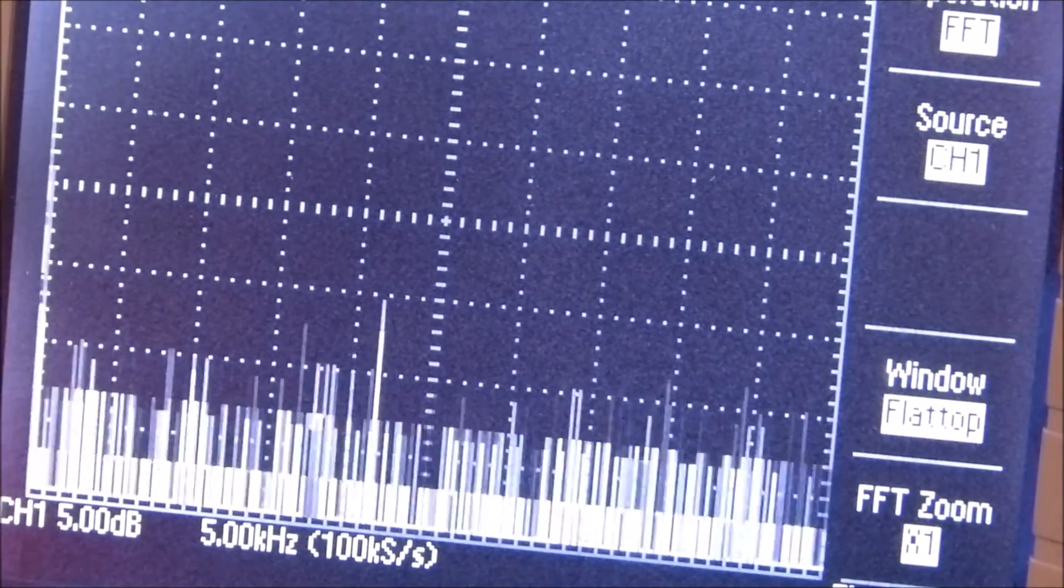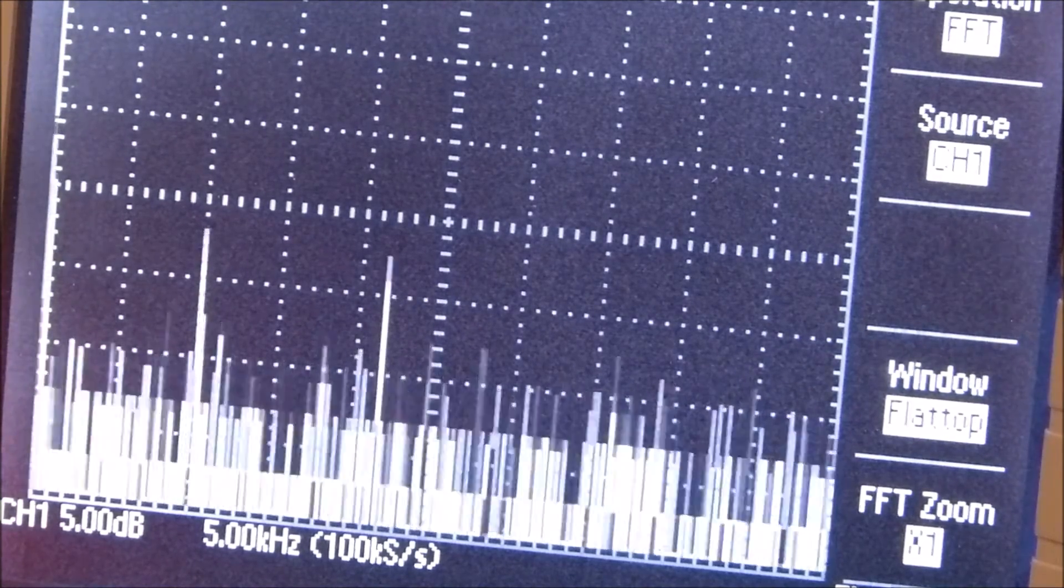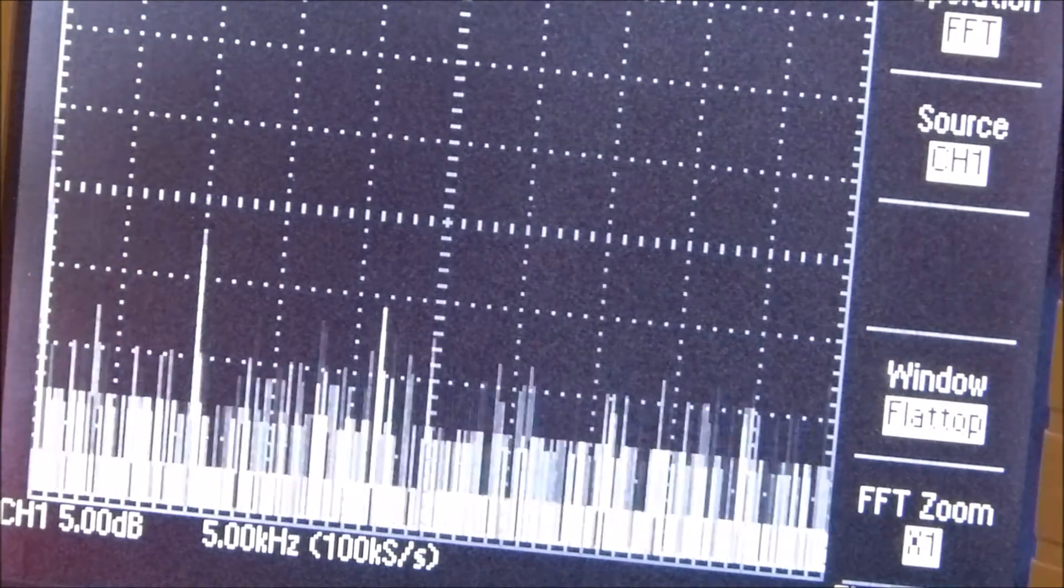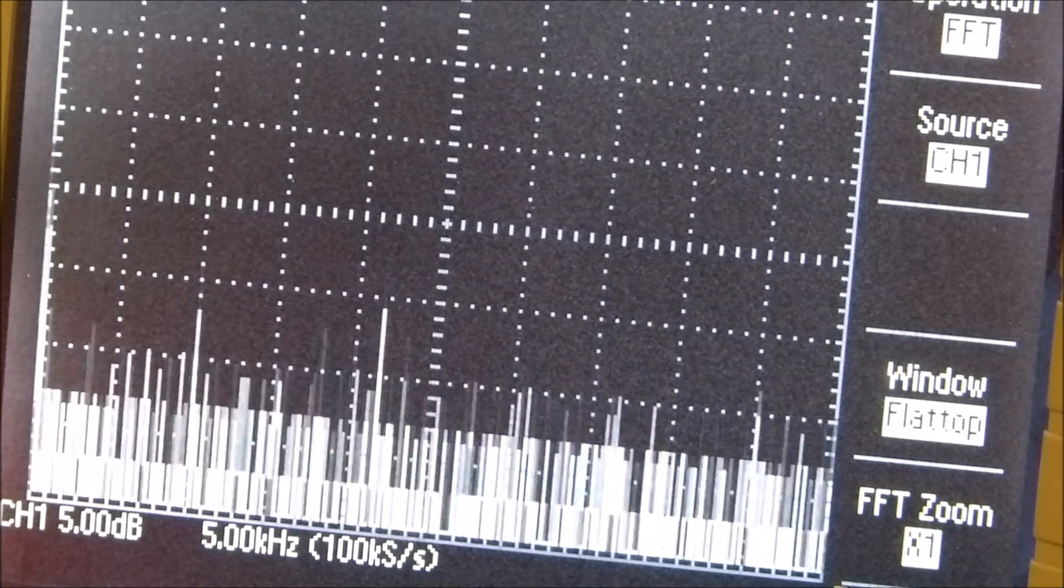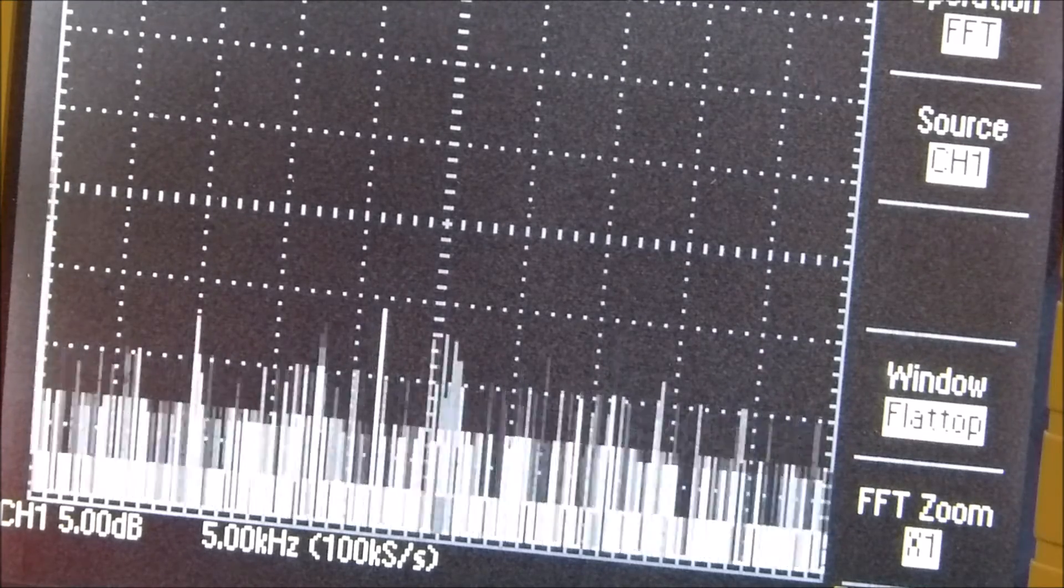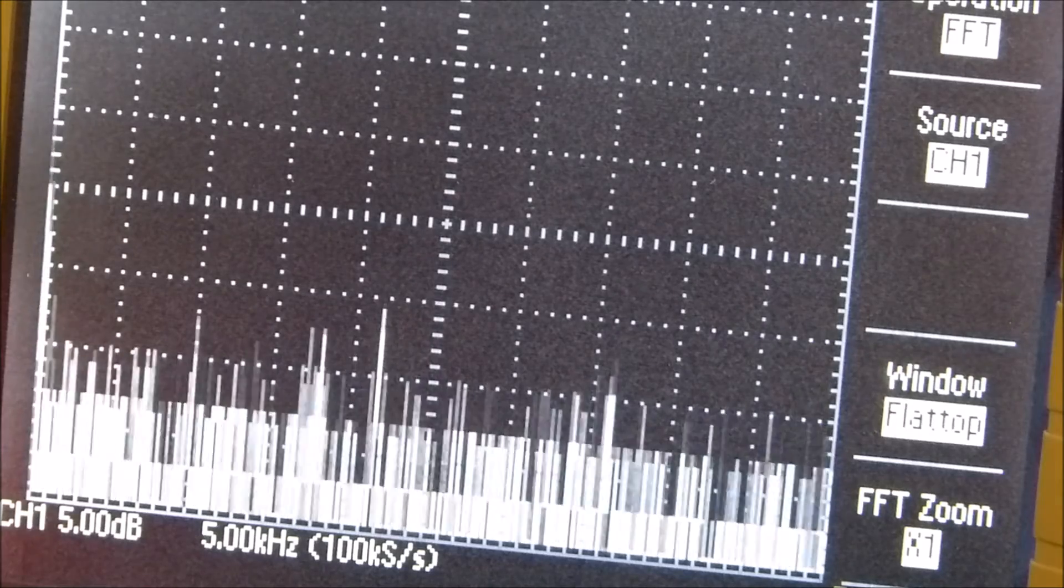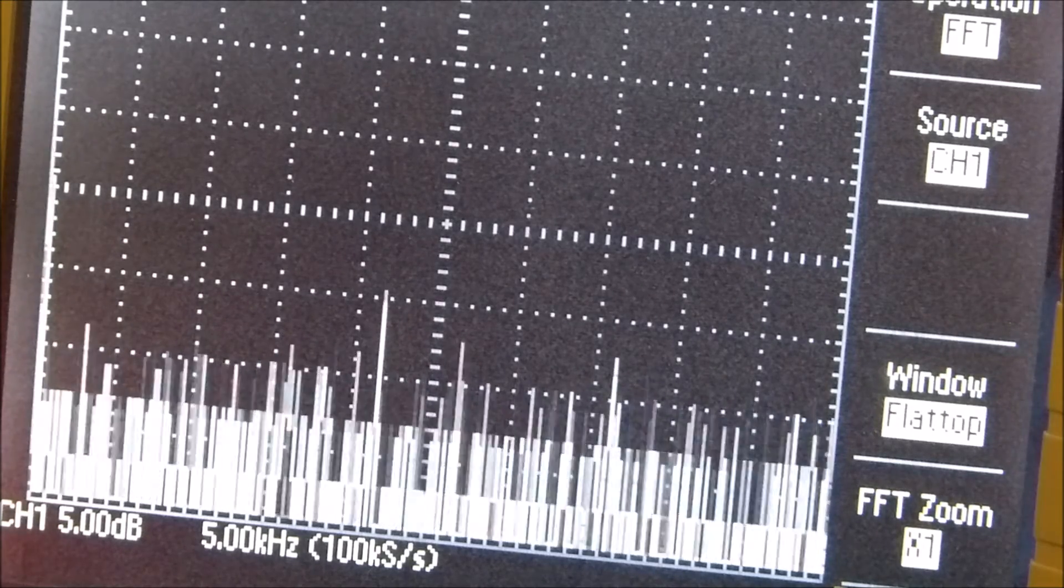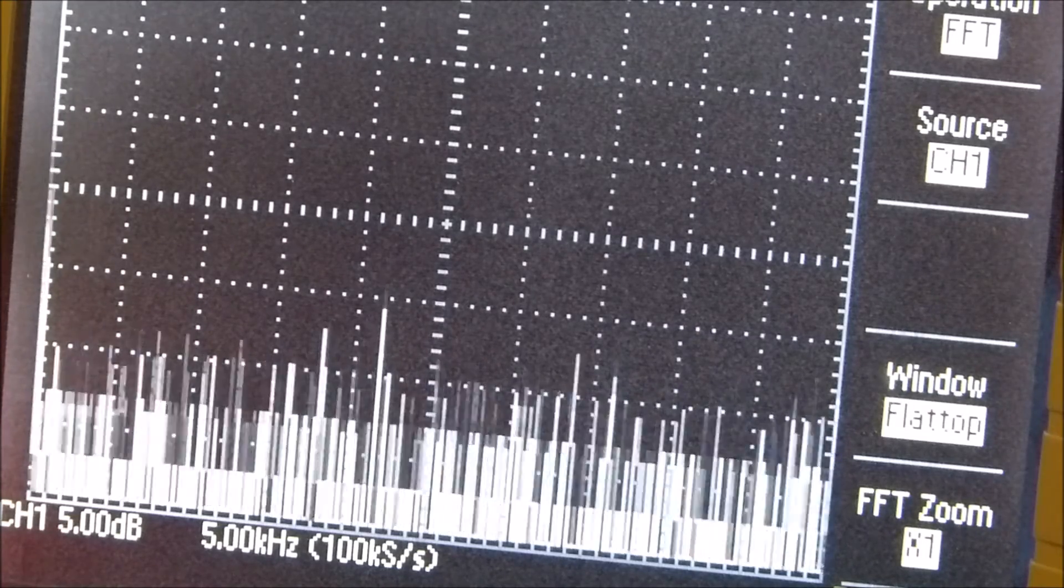If we look over here, of course this guy's going to show it balanced too, but there's so darn much noise. I'll crank it back up. I'm going to knock them both out of balance again so I can't cheat here. So we can see it again - there it is right there. Kind of hard to see, but I'm going to balance it as best I can.